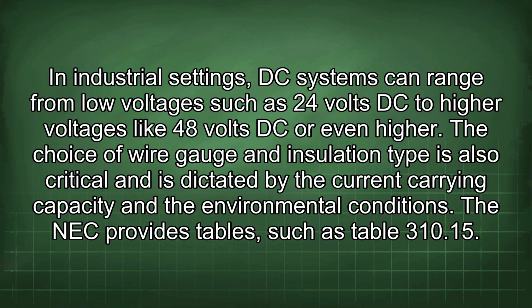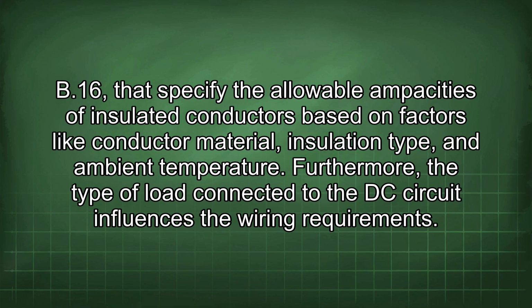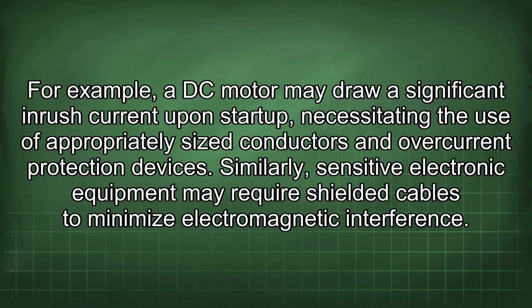The choice of wire gauge and insulation type is also critical and is dictated by the current carrying capacity and the environmental conditions. The NEC provides tables such as Table 310.15(B)(16) that specify the allowable ampacities of insulated conductors based on factors like conductor material, insulation type, and ambient temperature. Furthermore, the type of load connected to the DC circuit influences the wiring requirements. For example, a DC motor may draw a significant inrush current upon startup, necessitating the use of appropriately sized conductors and overcurrent protection devices. Similarly, sensitive electronic equipment may require shielded cables to minimize electromagnetic interference.